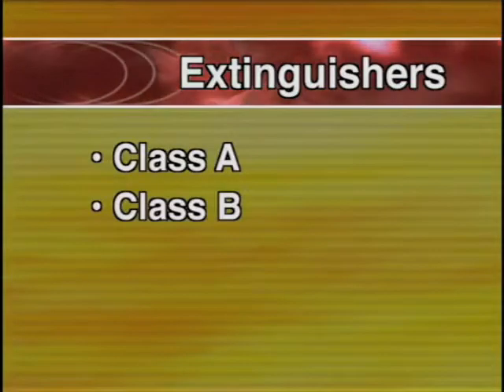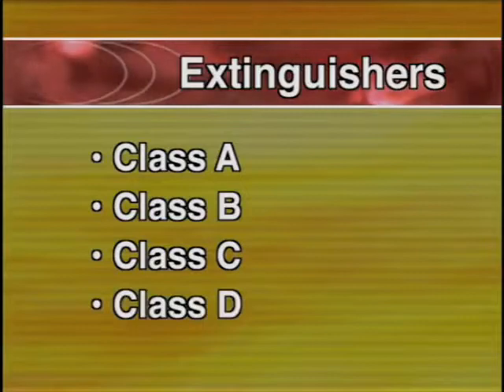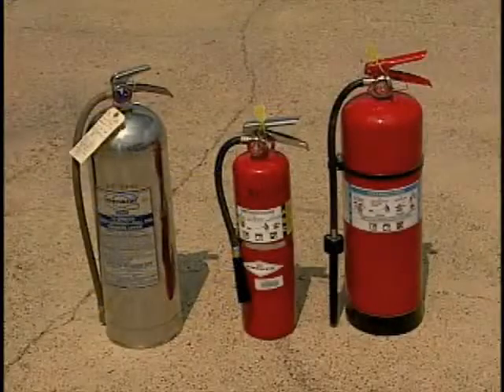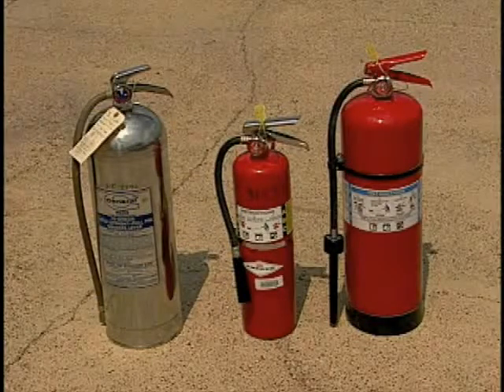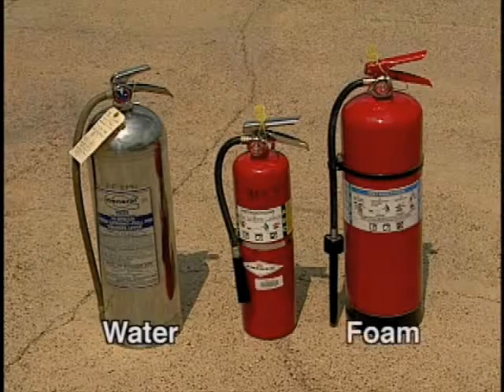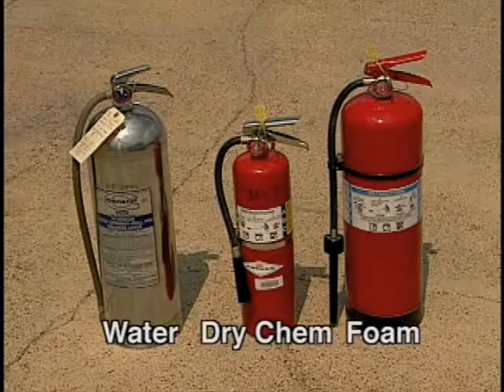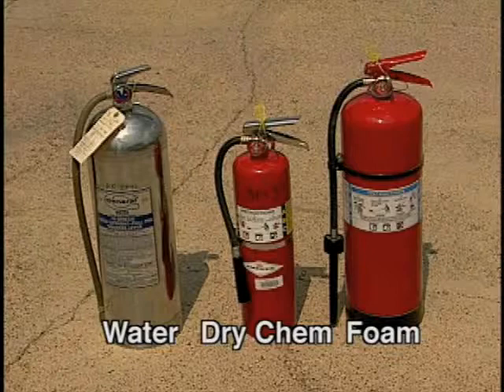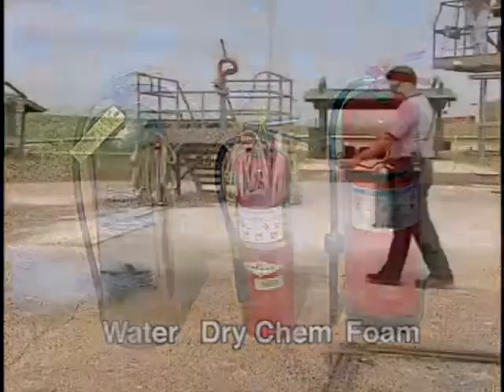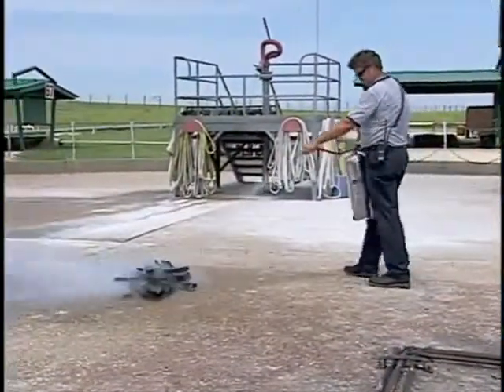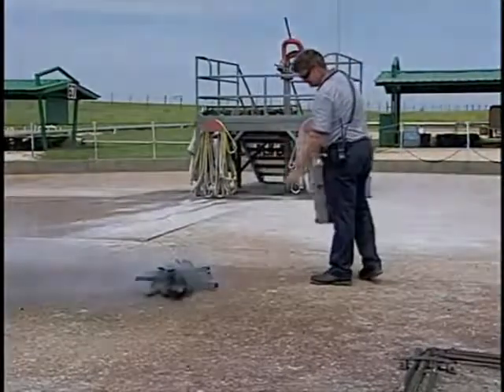Just as there are 4 classes of fire, there are 4 corresponding classes of extinguishers: Class A, Class B, Class C, and Class D extinguishers. Class A extinguishers are extinguishers that use pressurized water, foam, or multi-purpose dry chemical. Class A extinguishers are used on Class A fires. These types of fires include common combustible materials such as wood, paper, rubber, cloth, and most plastics.